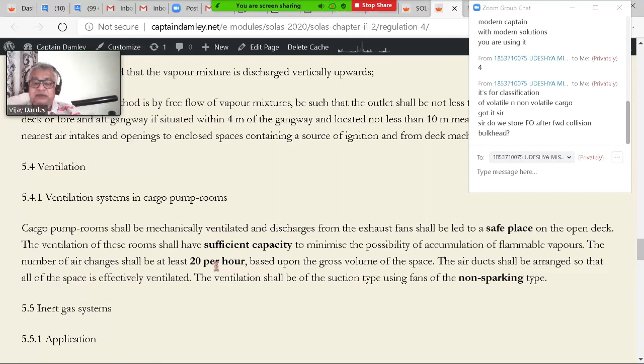It sounds good. Anyway, in spite of having this sort of arrangement, the moment you switch on the light, the pump starts, ventilation starts, we still get people dying in pump rooms. Still. No logic, it has failed completely. You have a hydrocarbon detector, which is telling you yes, there is gas inside. Everything is there. Still people try to become hero. But remember, here it is a question of 10 minutes time. You should have safety in any way, because this capacity is really very, very high.